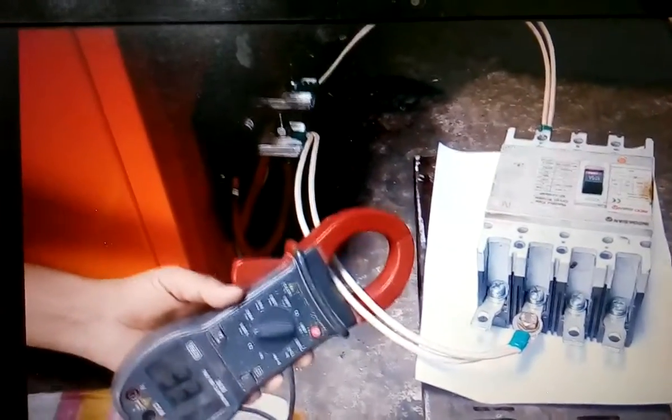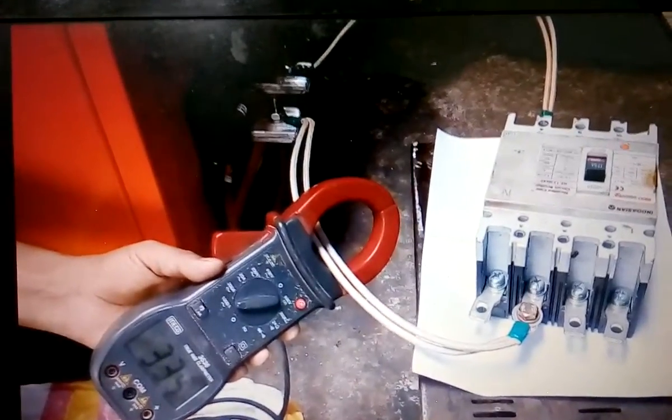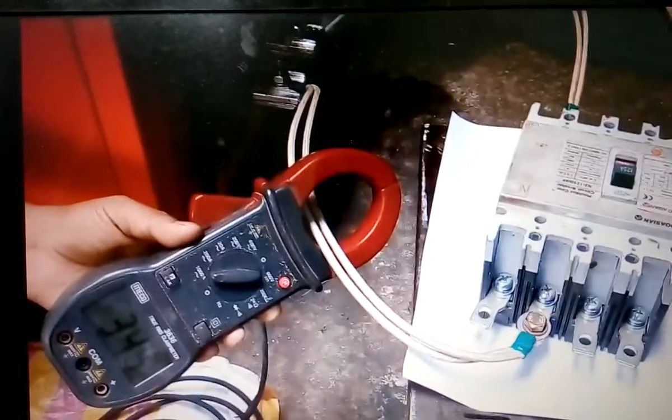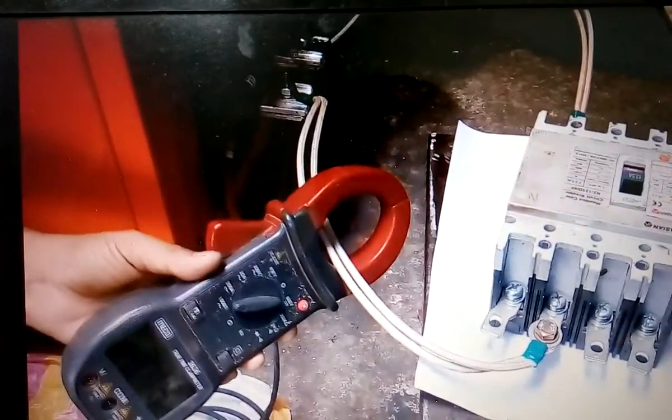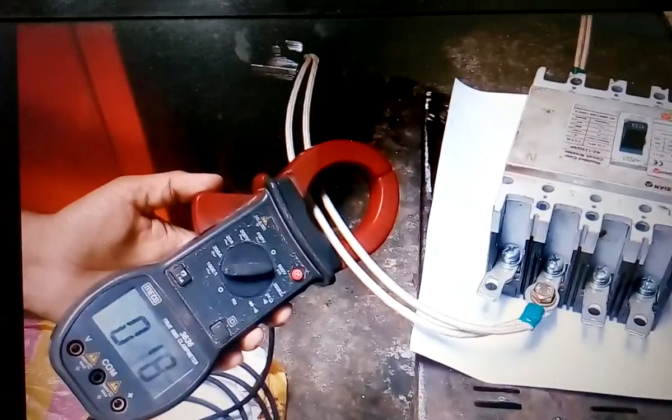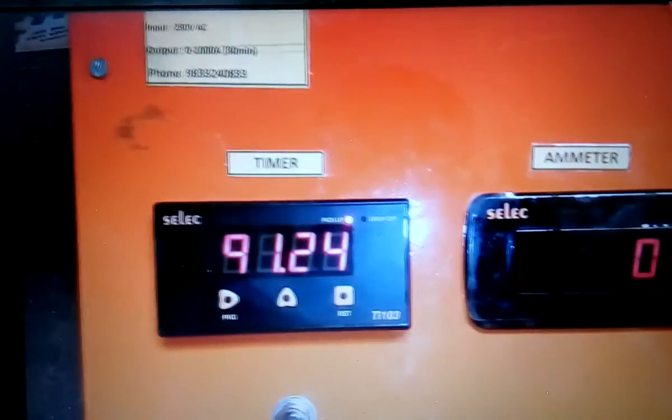The tripping must have initiated, but due to thermal characteristics it will take time to trip. It has got trip now. Got trip. Zero ampere. Now 91 seconds. So 91 seconds, we have stopped the timer. The MCCB has already tripped.